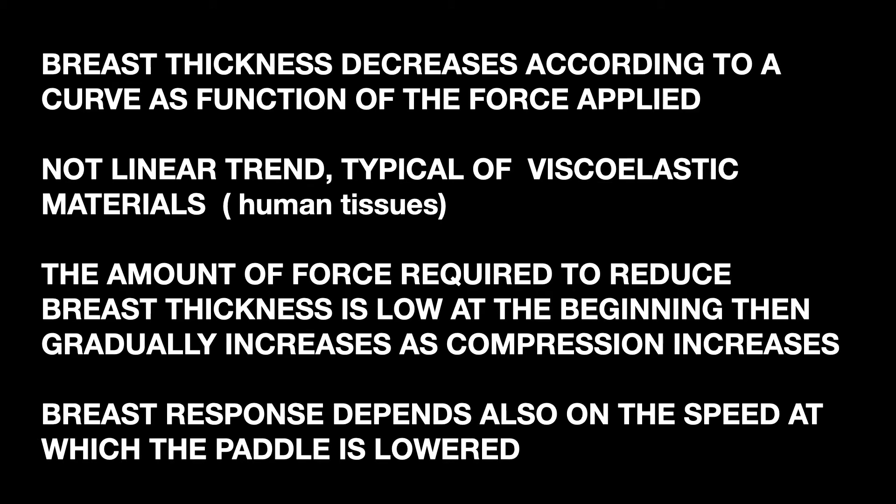The breast thickness decreases according to a curve as a function of the applied force, following a non-linear trend characteristic of viscoelastic materials — materials which, under the action of a force, have a behaviour intermediate between that of soft solids and that of fluids. Human tissues belong to this category. The amount of force required to reduce the breast thickness in millimetres is low at the beginning and then gradually increases — more and more force is needed to achieve a further reduction in thickness after a certain value.